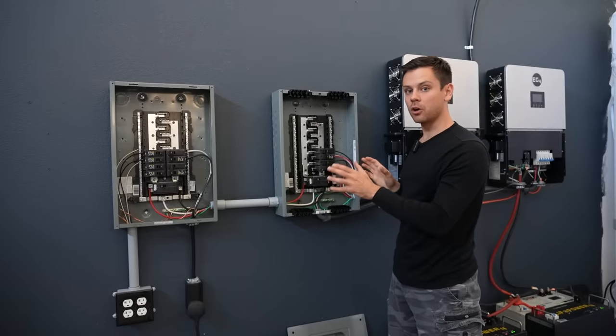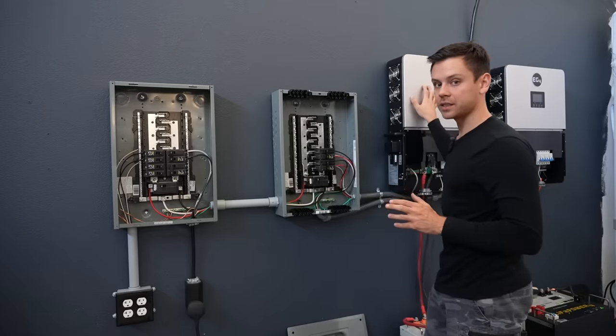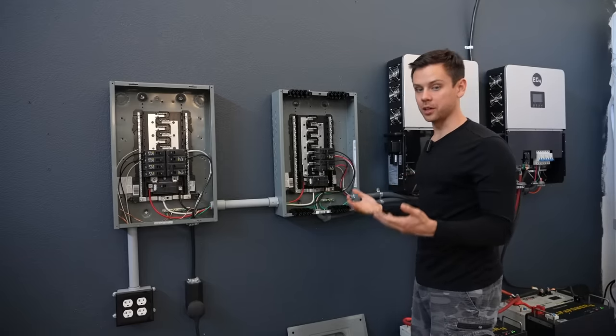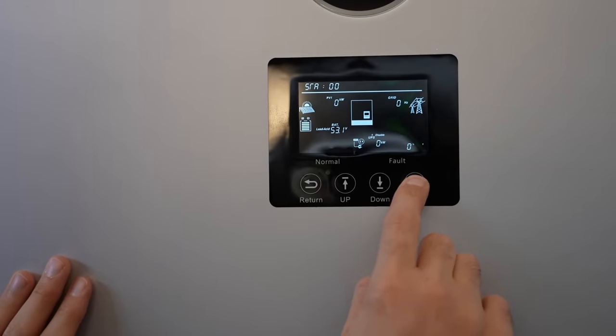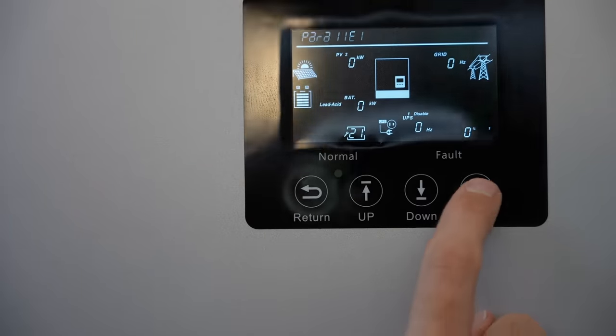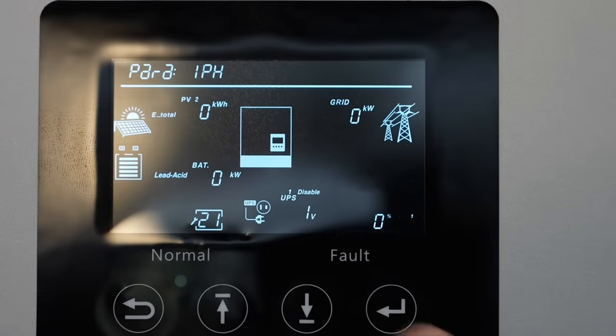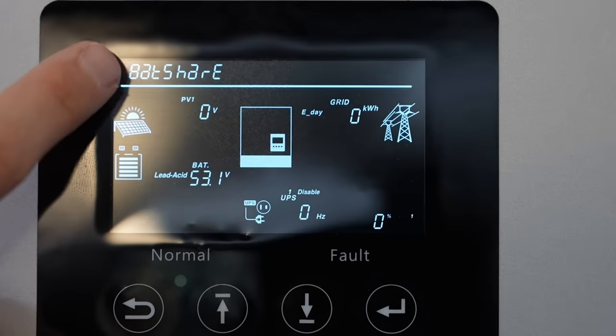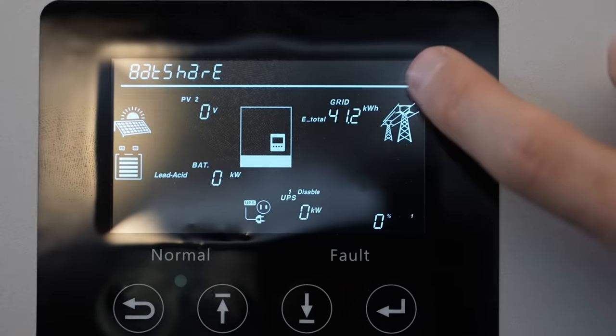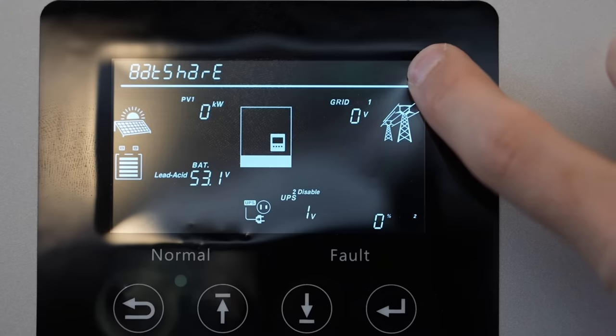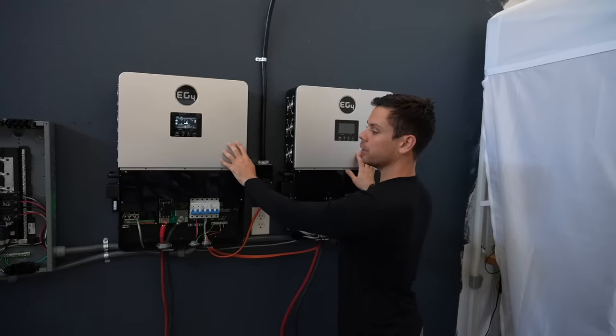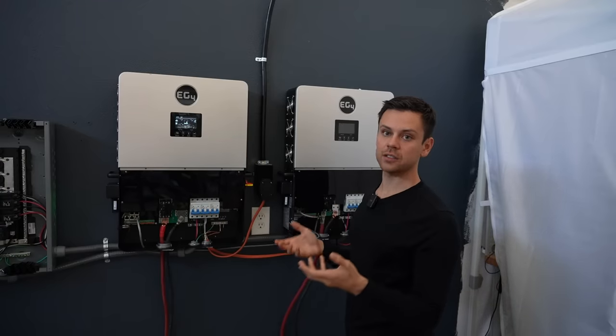Now that everything's wired let's talk about the programming. All you have to do is change a couple settings on the 6000 XP and they will be in sync so you can run loads together and double your output capacity. First hold down enter until you reach the settings. Go down to setting number 21 and then press enter. You want to select one PH and then press enter. And then P1 and then press enter. And then battery share because they're all connected to the same battery. You want to enable it. It comes disabled but make sure that you enable that. And then press enter and that's it. It will flash which means it updated the settings.